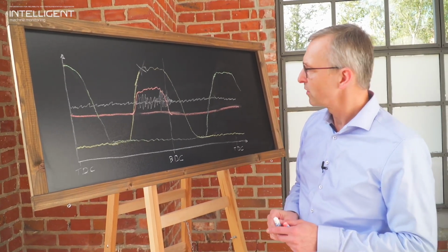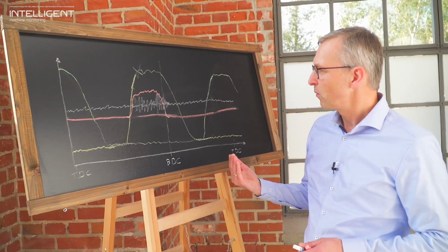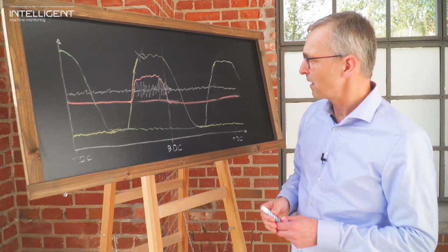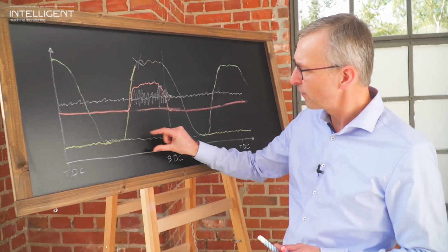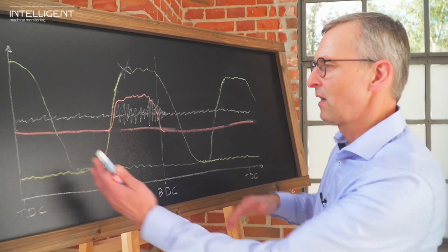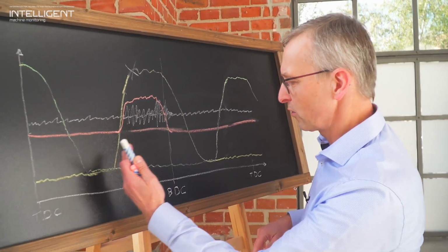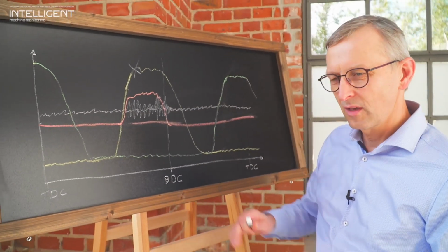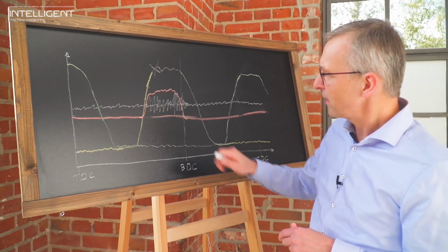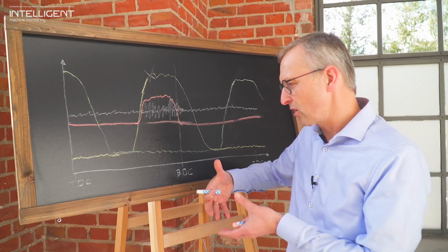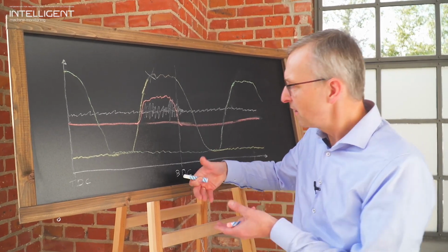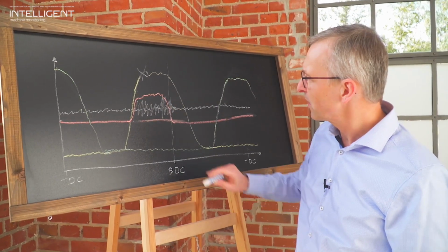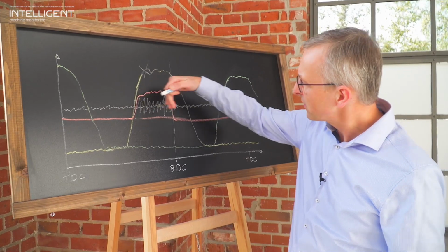Now, how is this connected? What we have found in the past is that we are compressing the gas. There is some fluid in the bottom of our cylinder, and when we are coming closer to bottom dead center and to the point of discharge, the pressure on this fluid is getting high, and in the same moment some of the fluid is actually going underneath our piston, lifting the piston up, and this is what we see here with our rod position measurement. The piston is being lifted up for the rest of the revolution.